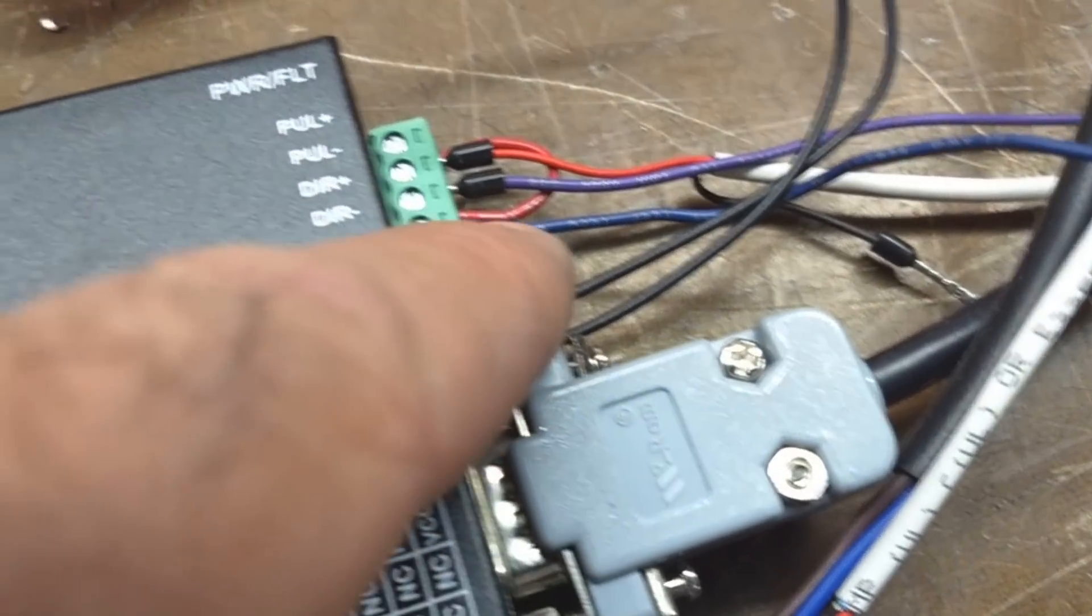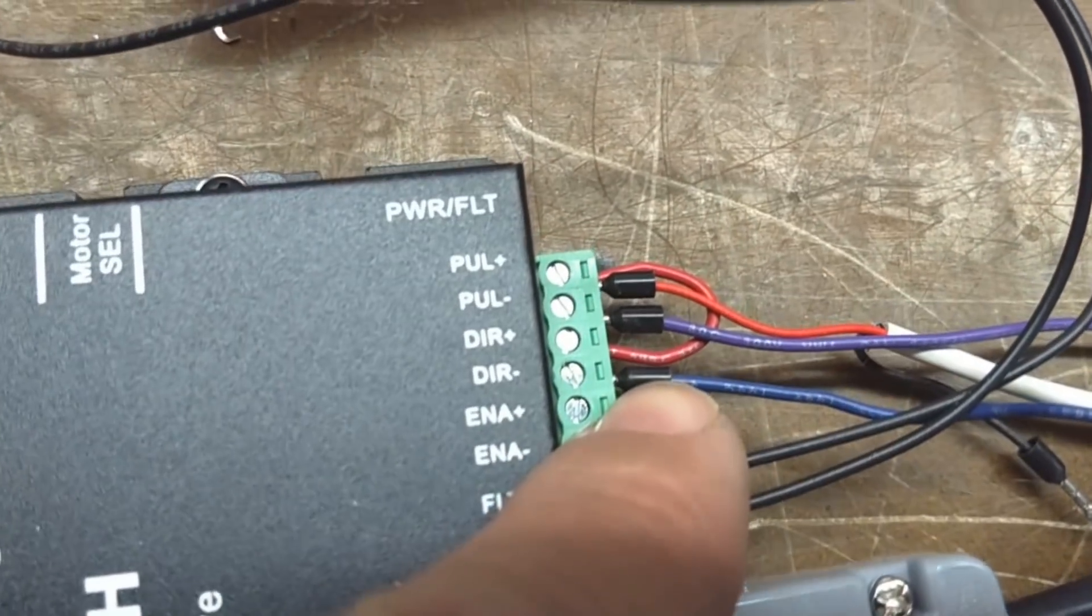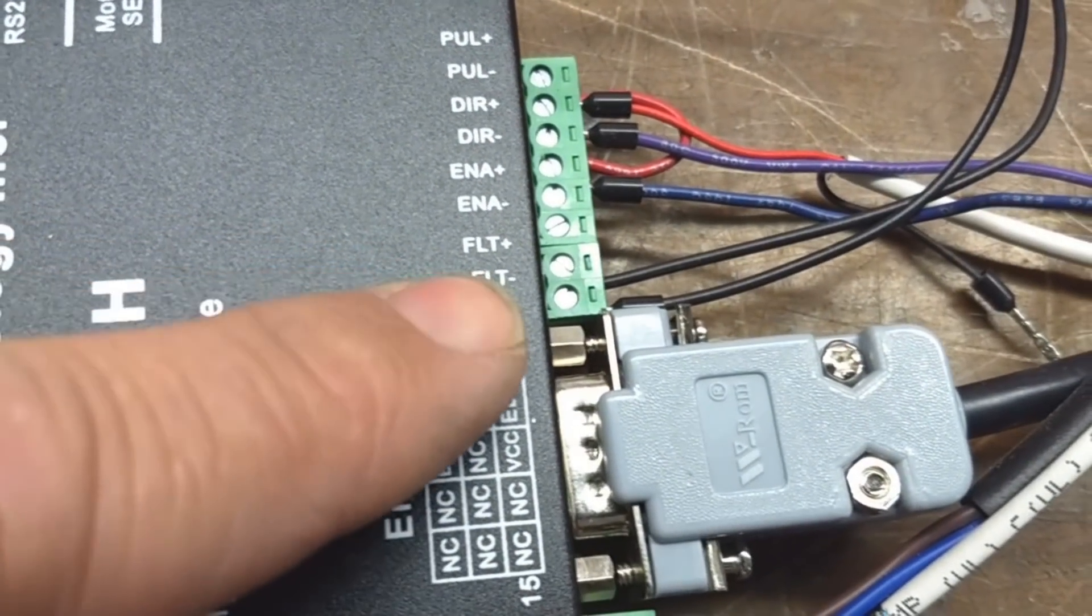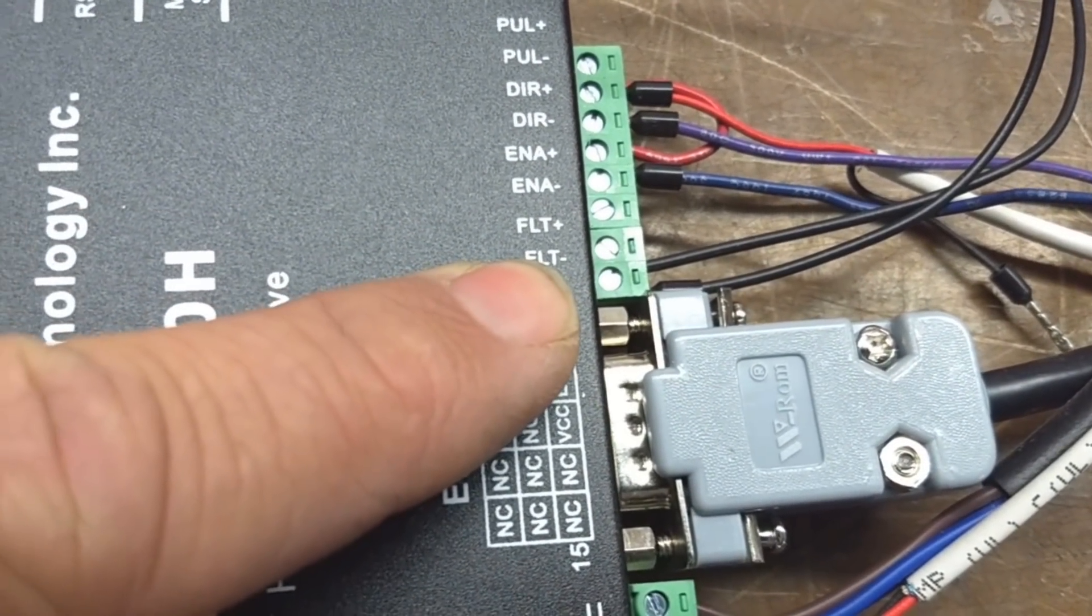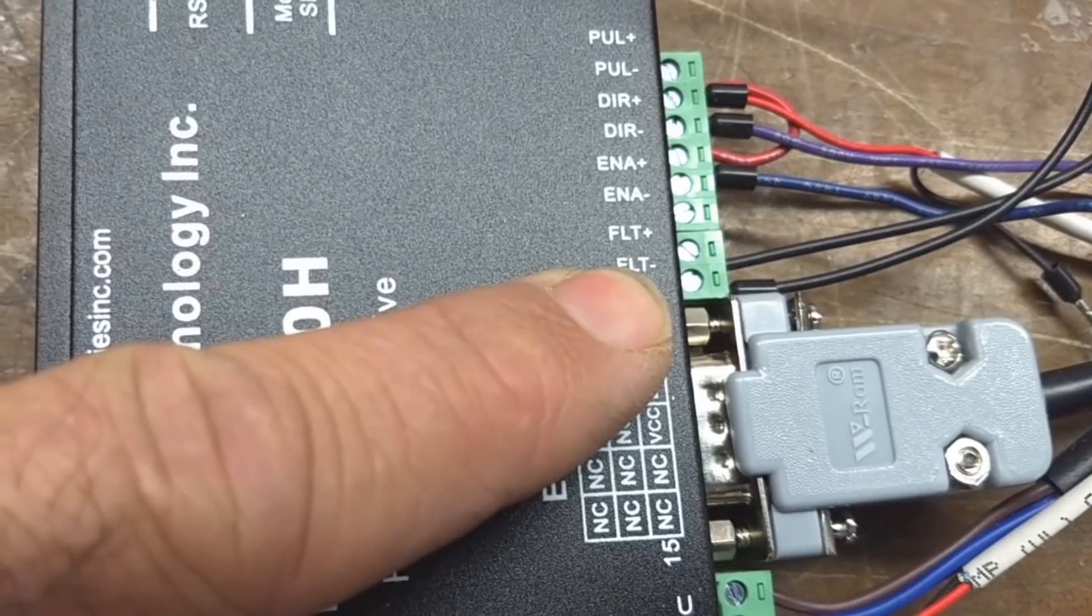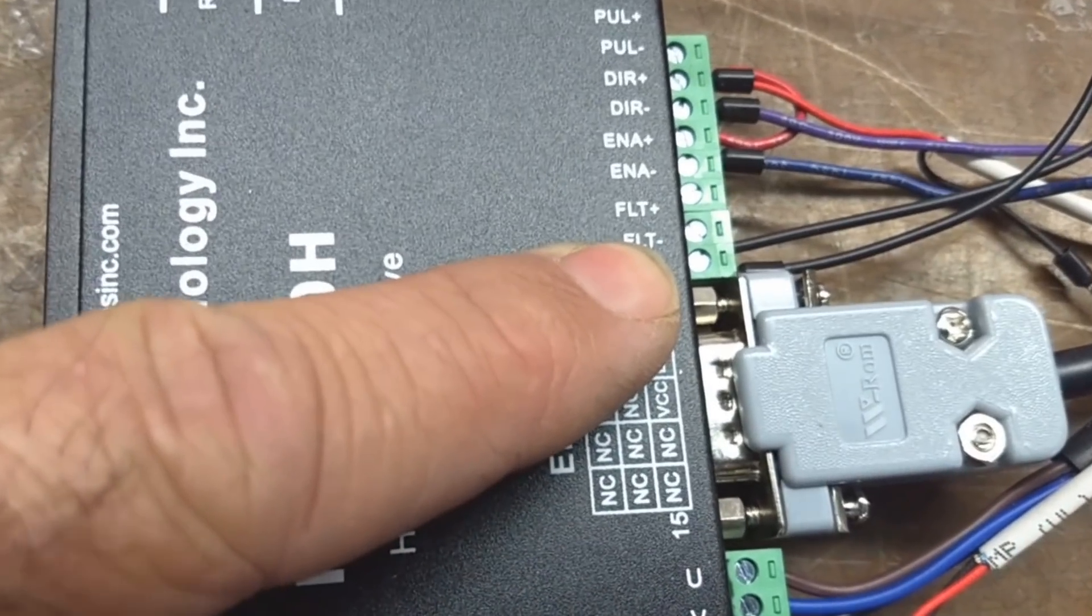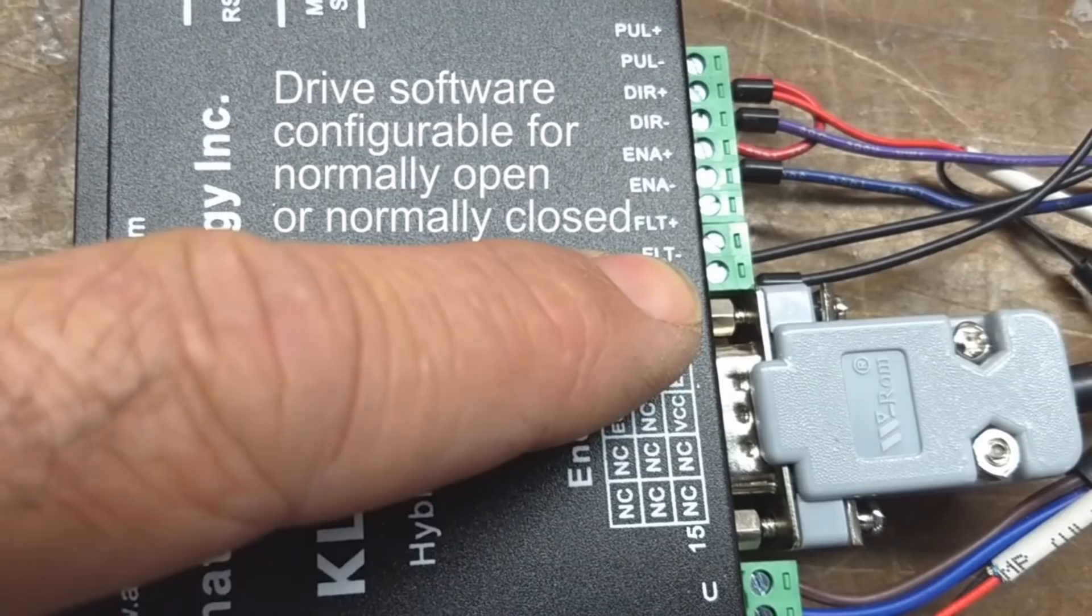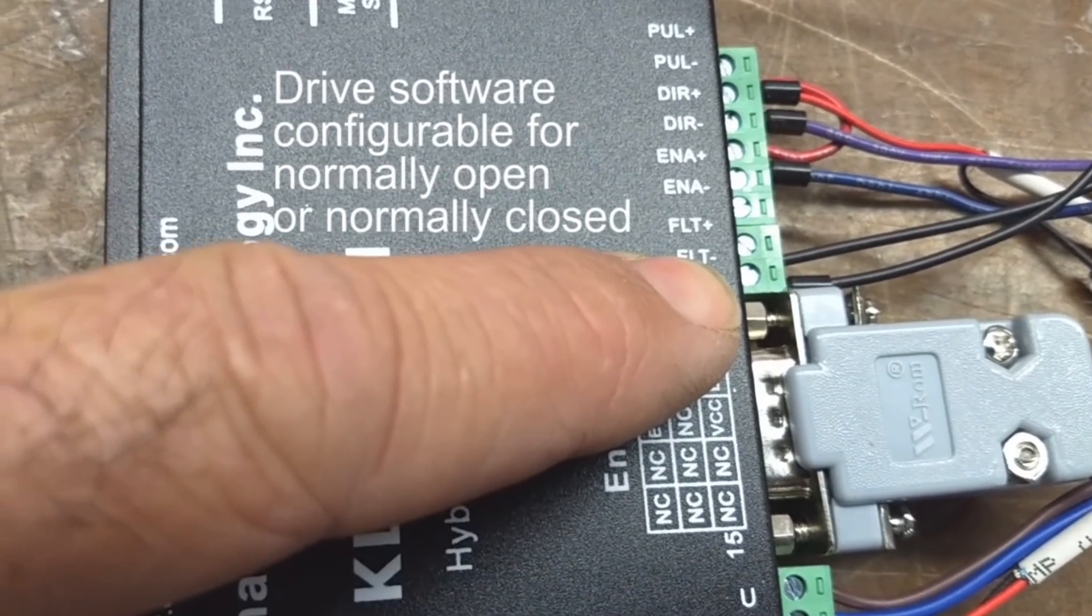It comes around and it goes into direction negative on the drive. And then here the fault, the alarm output, it is a normally open output. It closes when there is a fault.